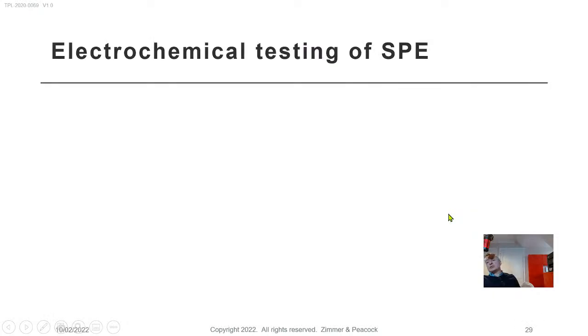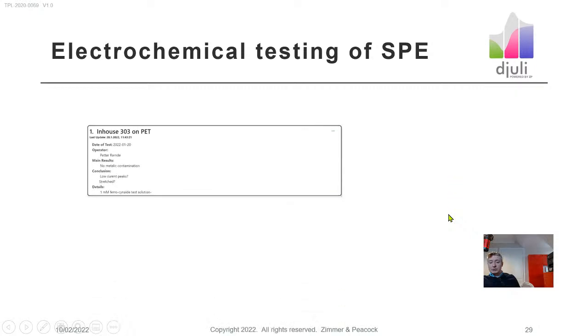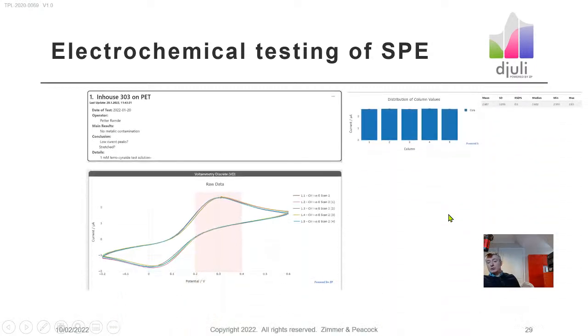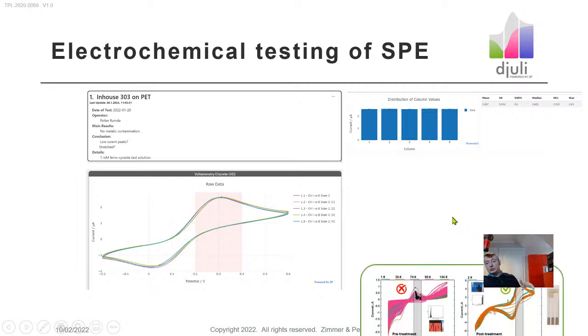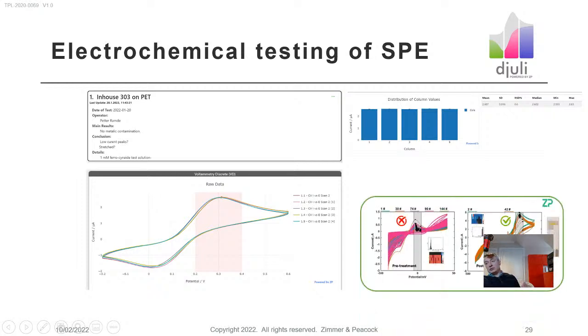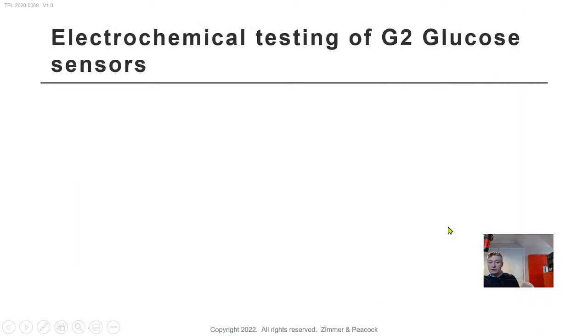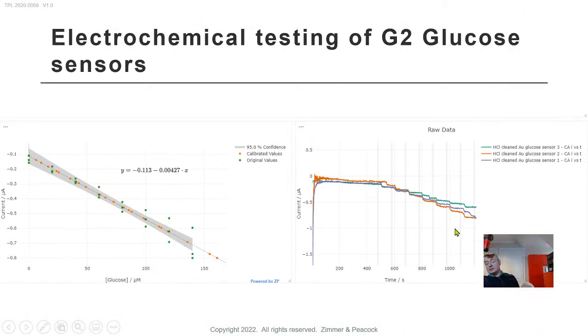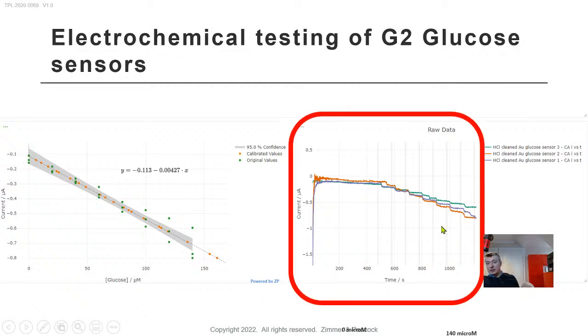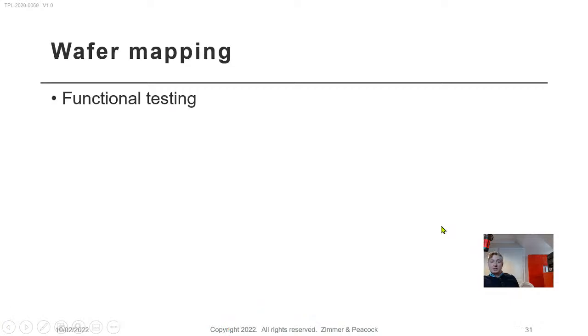We do something else, which is electrochemical characterization of the screen printed electrodes. Again, Djuli allows us to do this at very industrial scale. We are able to test a lot of screen printed electrodes in parallel. We upload the data to Djuli. Djuli does the statistical analysis and allows us to accept or reject batches of screen printed electrodes. And if the electrodes become a biosensor, it allows us to analyze and reject biosensors. In this case, I'm looking at a G2 glucose sensor.